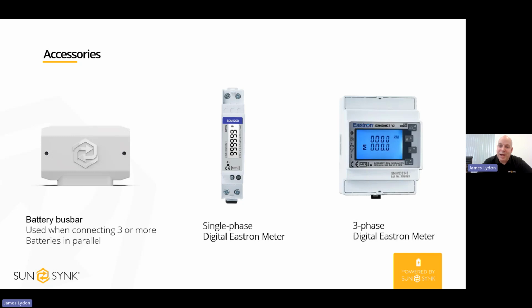So what you can do is add an Eastron meter to the AC coupled system, which connects back to our inverter, and then we put the CT on the AC out from the grid-tied systems, and our system will intelligently add all the data up, so we can see what the grid-tied inverter is generating. We know what's going to the grid and what the house is using. So yeah, it's not essential to use that, but in terms of having all the data correct, we do recommend it.